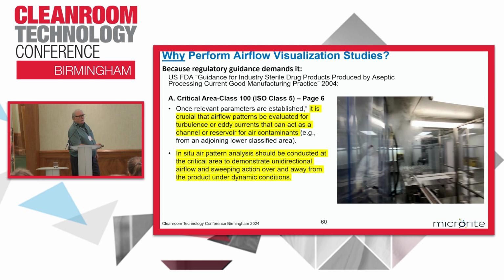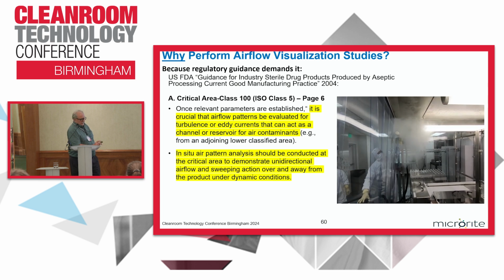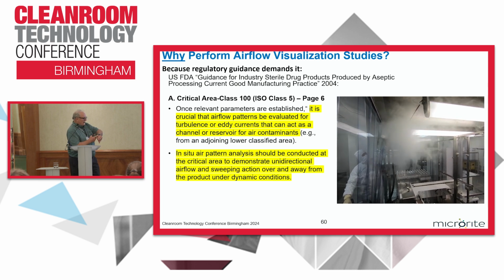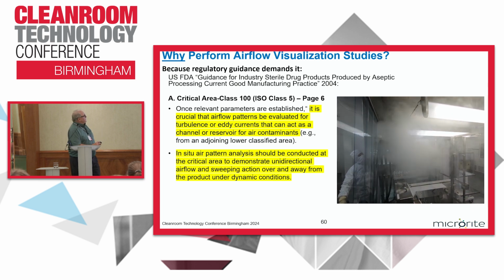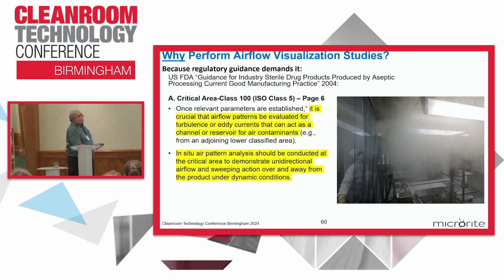Why do we do the studies? Well, we do these studies, number one, because we're required to. The US FDA requires us to do airflow visualization. And one of the important concepts to remember is, again, from the US FDA sterile aseptic guidance, it is crucial that airflow patterns be evaluated for turbulence or eddy currents that can act as a channel or reservoir for contaminants.